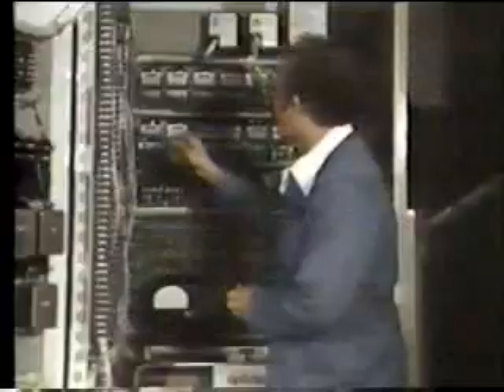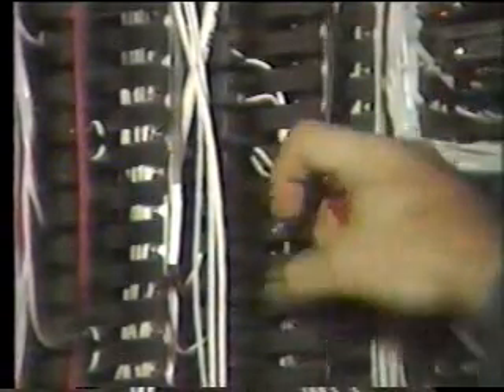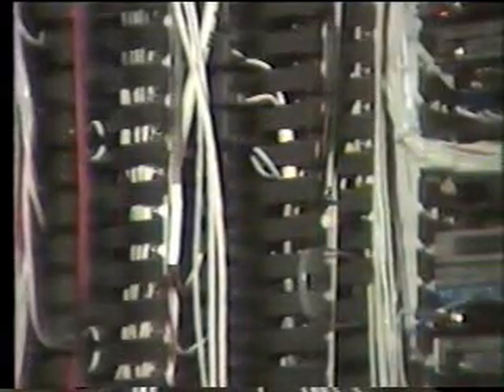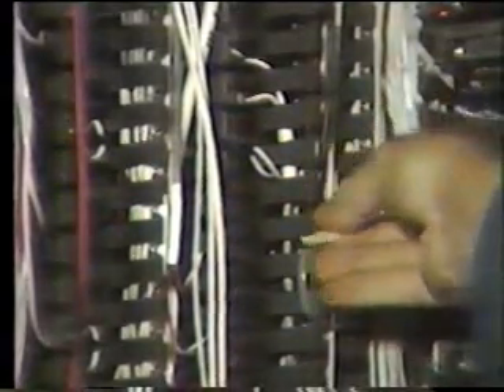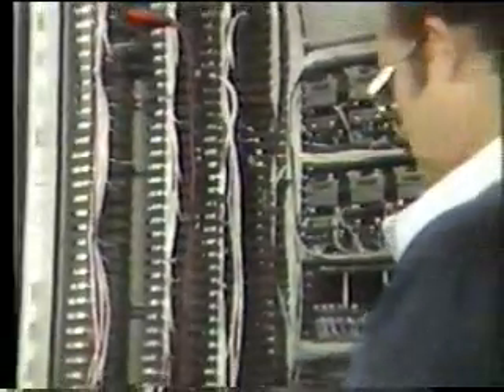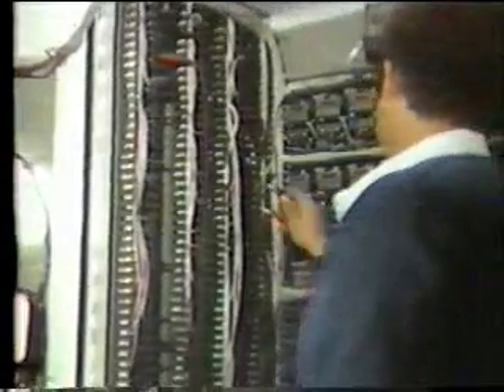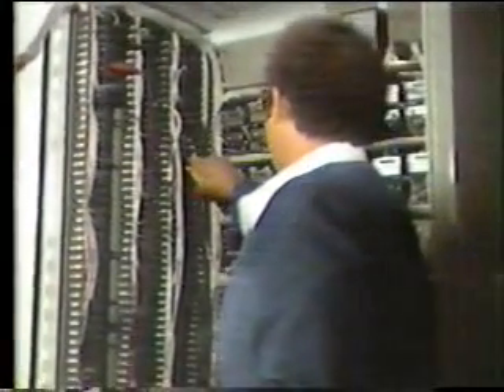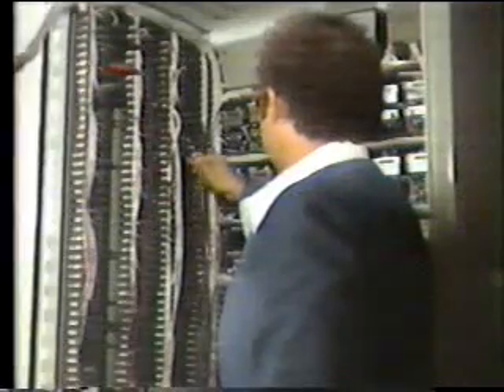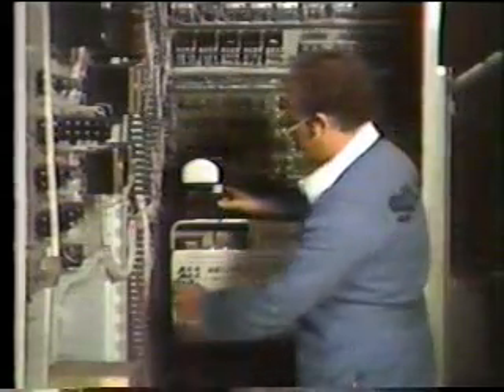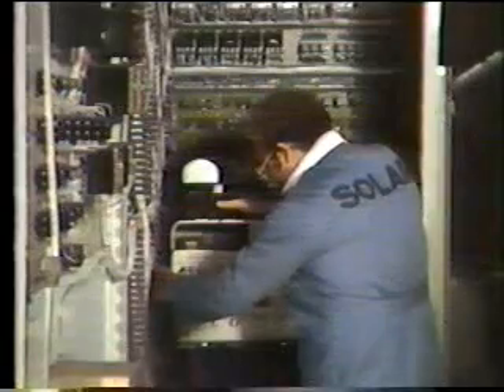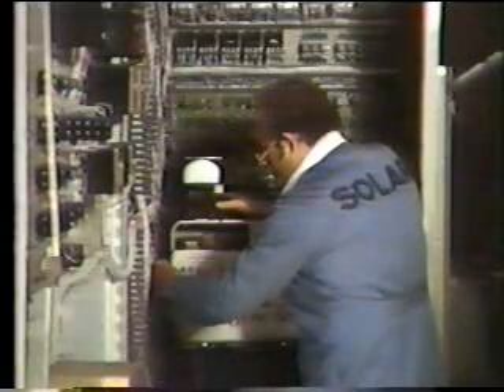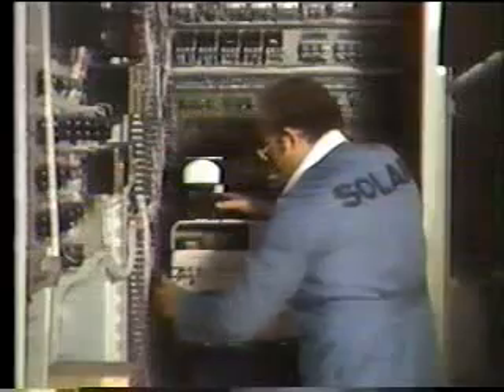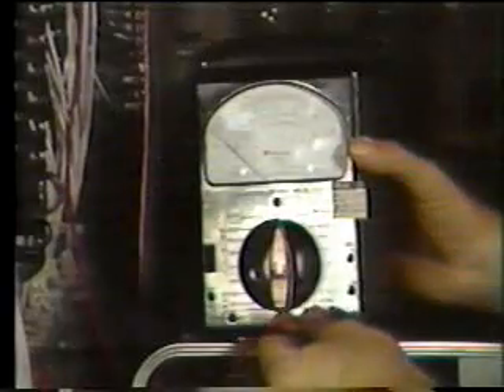Then disconnect the lead that goes to the magnetic pickup from the terminal strip. Tape the lead to prevent it from contacting the other circuits. Now connect the output leads of the signal generator to the terminal board wire that goes to the electronic speed monitor. Next, attach two additional leads to the source A signal generator. Attach the other ends of the leads to the input jacks of the VOM.